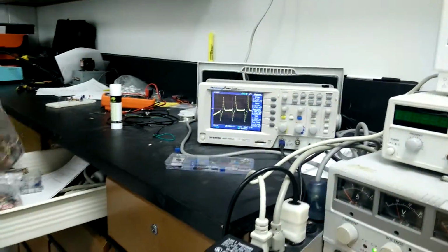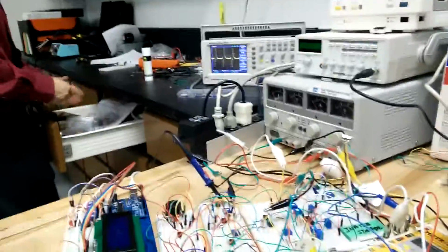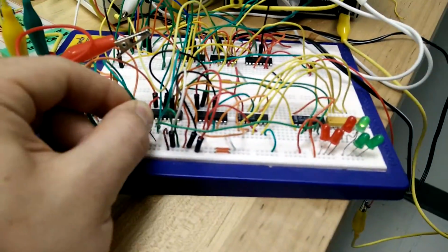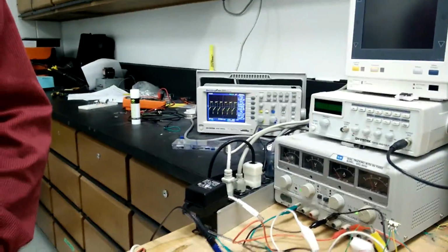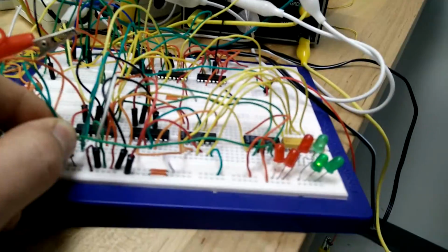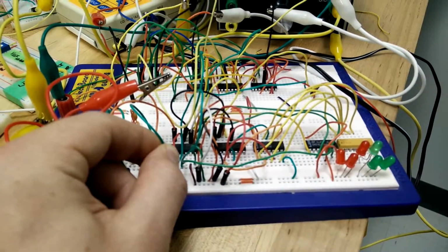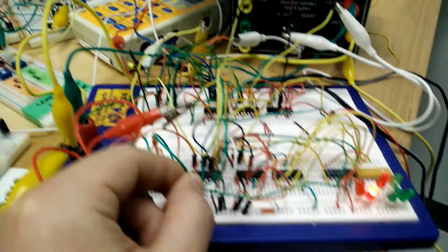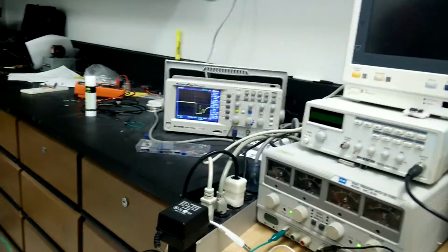This one is the patient sim, which is basically supplying the R wave for our circuit, as you can see. This is our 1 millivolt calibration pulse. And just the auto zeroing circuit, which you won't really see much output out of.